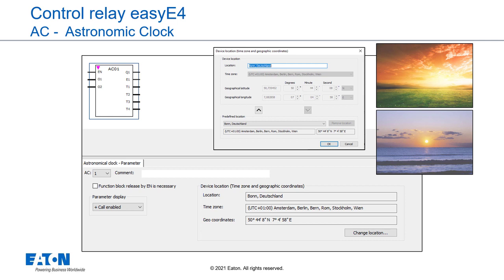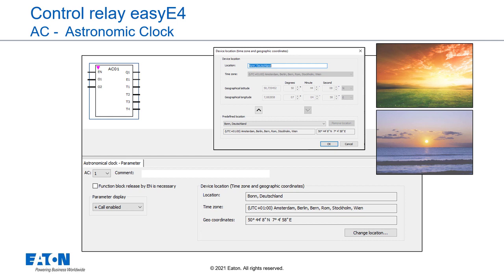At the function block inputs O1 and O2, a time shift for sunrise and for sunset can be specified respectively. That means that the time when Q1 will be switched can be moved up or delayed in order to, for example, implement the pre- or post-run for a heating control. If a daylight saving time is defined in the project view in the register clock, this is also taken into account for the switching of the function block output Q1. The resolution of the block inputs and block outputs is in minutes.